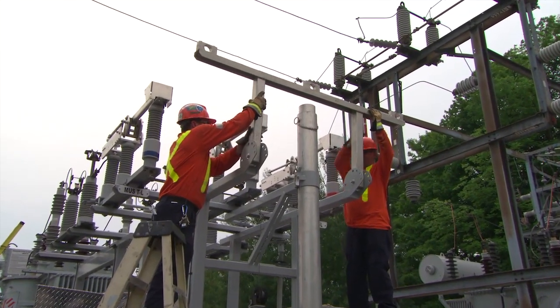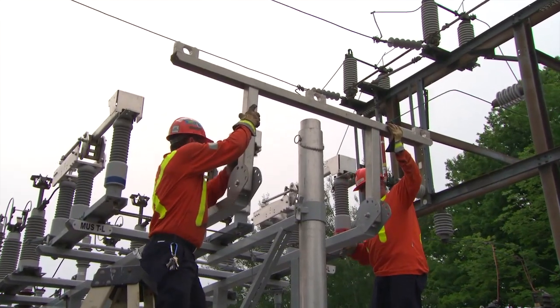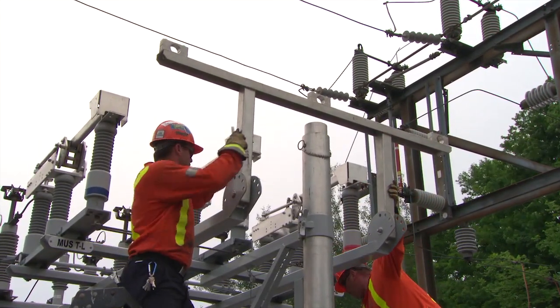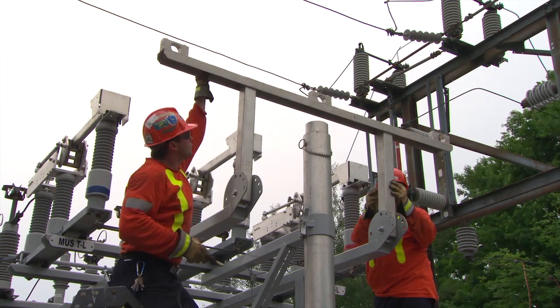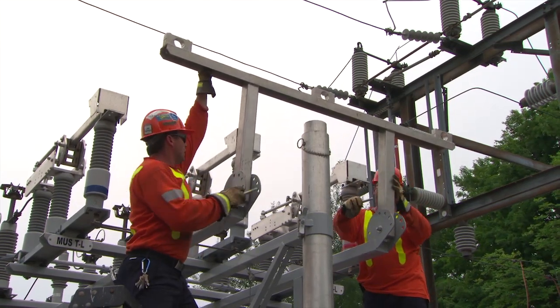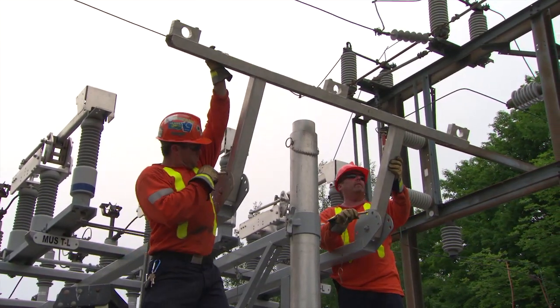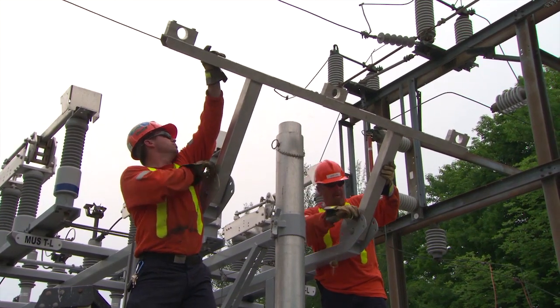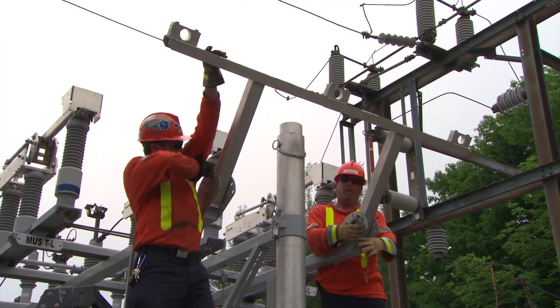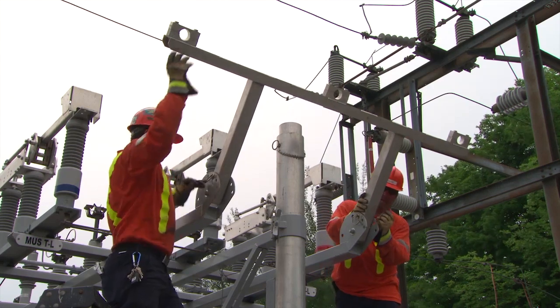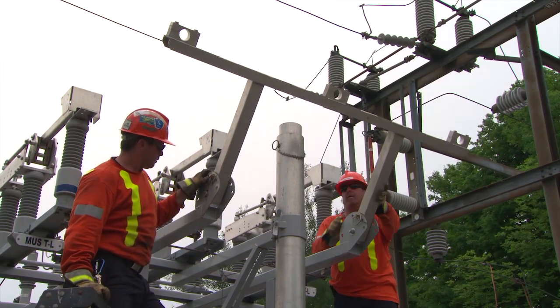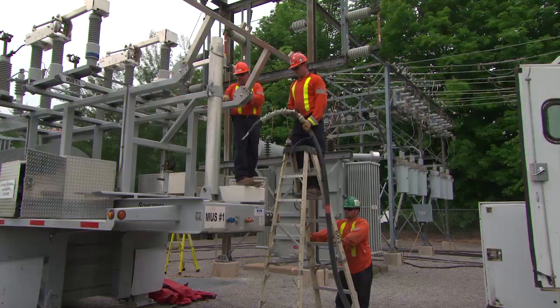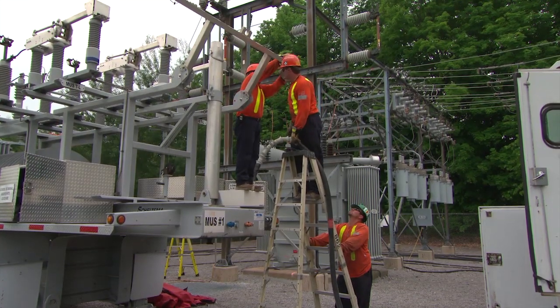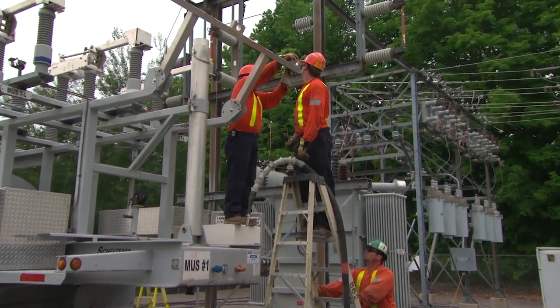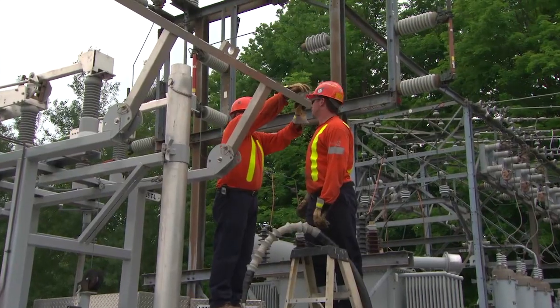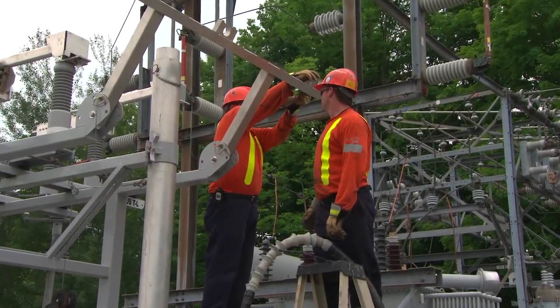Some 44 kV mobiles have high-voltage cables that can be used to connect the MUS high-voltage supply. Only mobiles equipped with a support bracket for these cables can use this method. This support bracket must be installed while prepping the mobile. Remove the hitch pins, raise the bracket to the desired angle, and then reinstall the pins. The high-voltage cables are then prepared, inspected, and tested the same way as the low-voltage cables and connected to the MUS after testing.